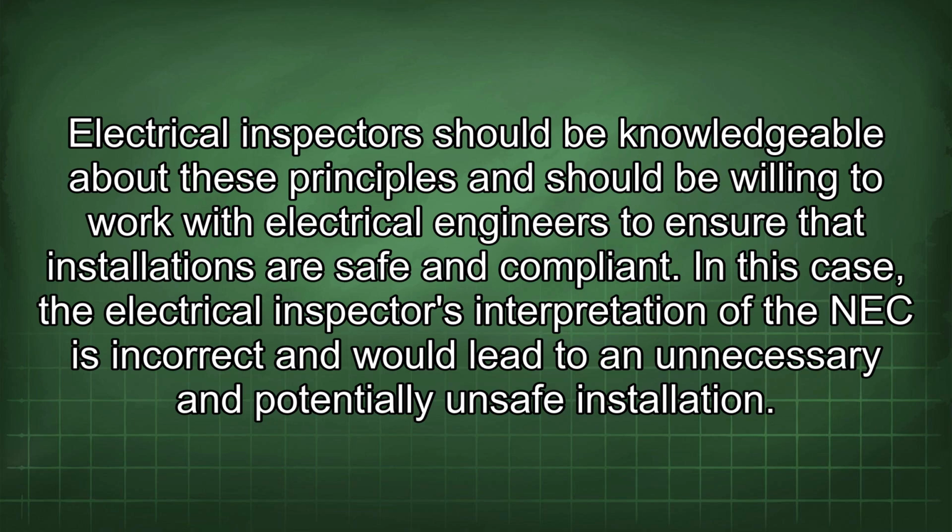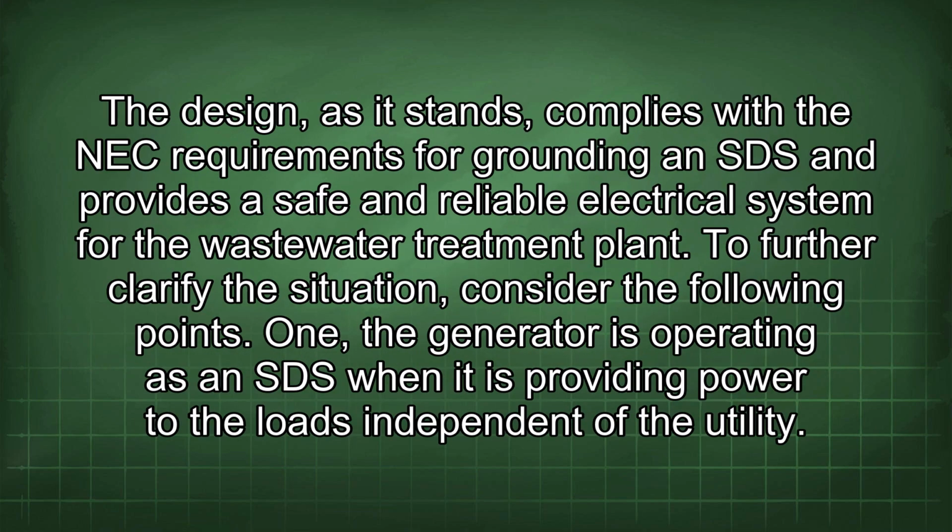In this case, the electrical inspector's interpretation of the NEC is incorrect and would lead to an unnecessary and potentially unsafe installation. The design, as it stands, complies with the NEC requirements for grounding an SDS and provides a safe and reliable electrical system for the wastewater treatment plant. To further clarify the situation, consider the following points.